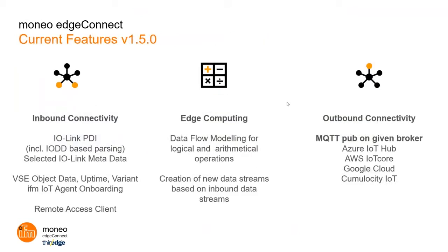One of the current features is inbound connectivity for IO-Link masters — in particular IFM IO-Link masters — but also smart devices for vibration analysis, specifically the VSE for particular use cases. The VSE consumes data from four sensors at 40,000 values per second each and reduces it to mechanical KPIs to understand what's going on with rotating mechanical equipment. It also has a remote access client.